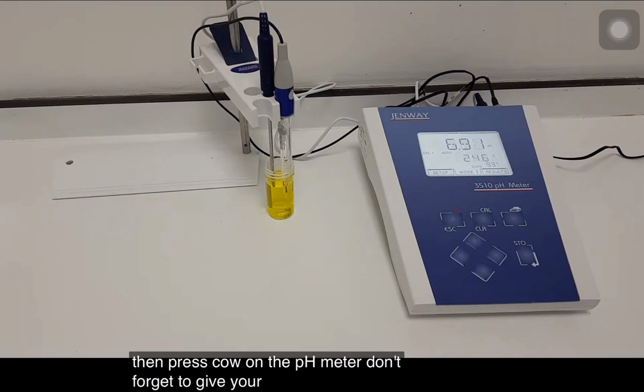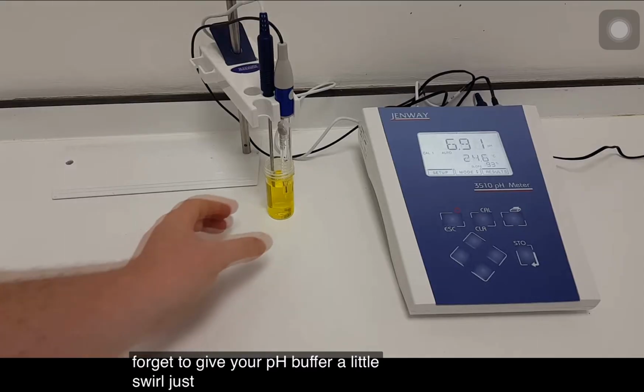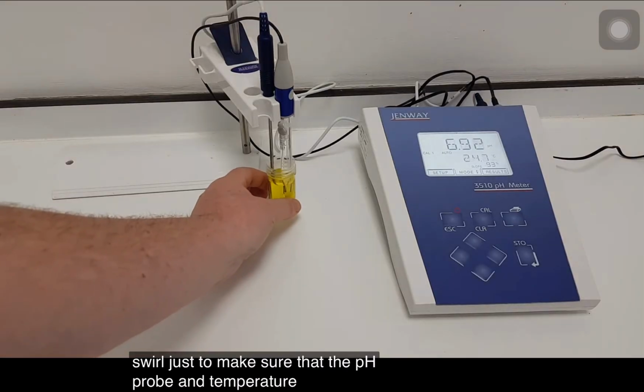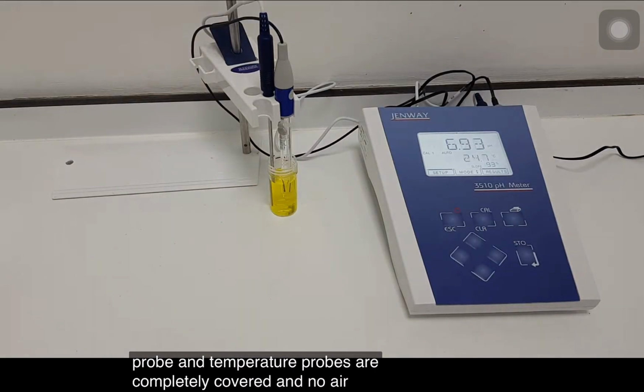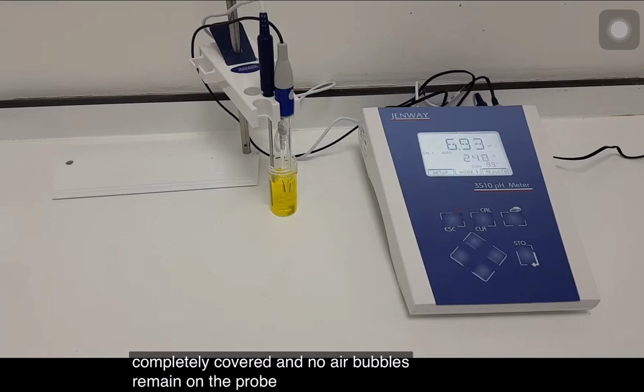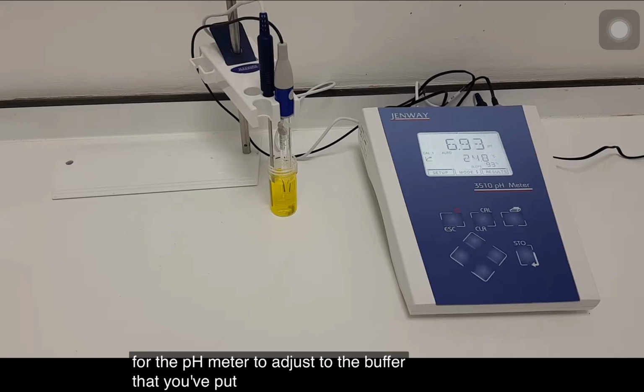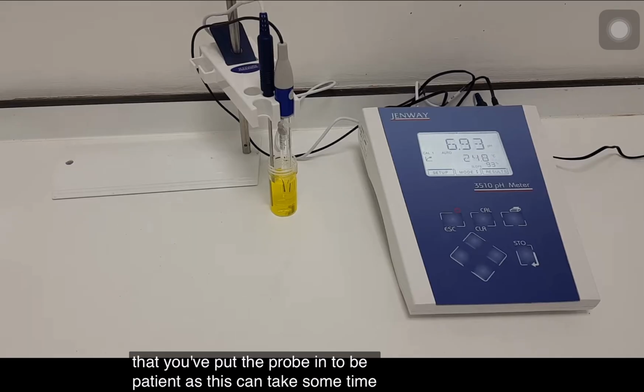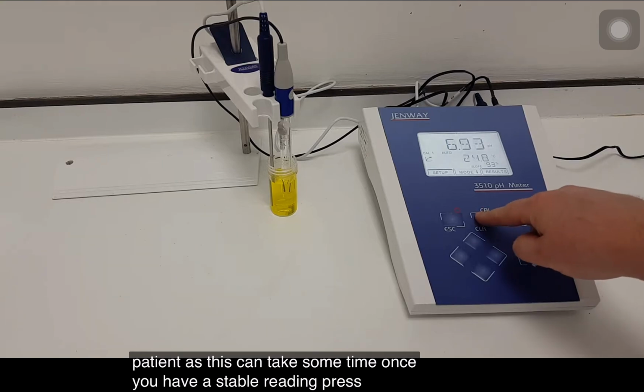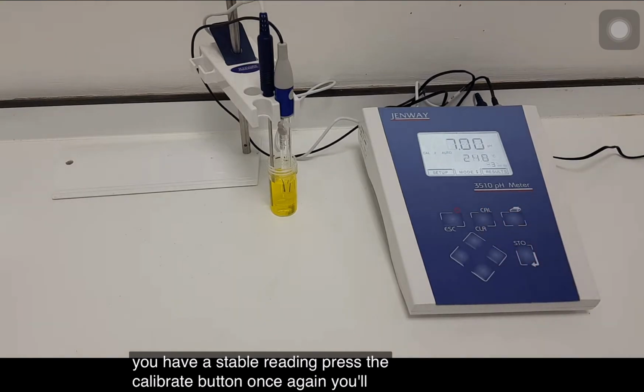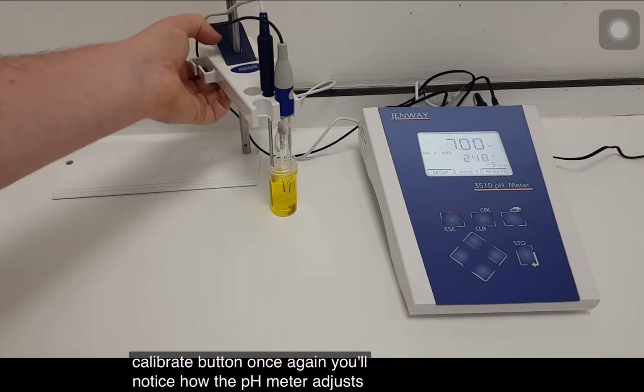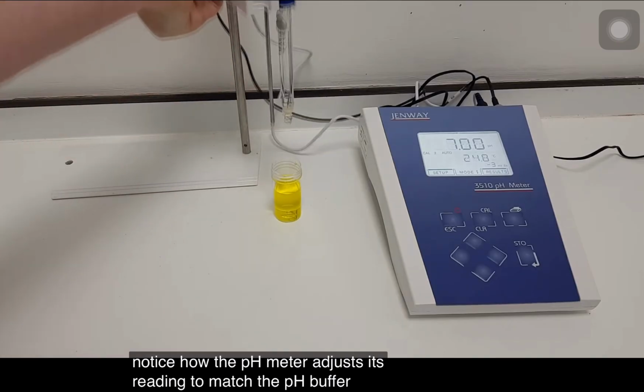Don't forget to give your pH buffer a little swirl just to make sure that the pH probe and temperature probes are completely covered and no air bubbles remain on the probe. You now need to wait for the pH meter to adjust to the buffer that you've put the probe into. Be patient, as this can take some time. Once you have a stable reading, press the Calibrate button once again. You'll notice how the pH meter adjusts its reading to match the pH buffer that you've used.